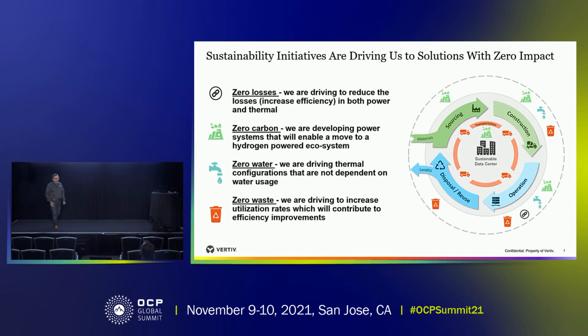One of the things we talk about a lot is UPS efficiency, or power system efficiency. You might see numbers quoted at 96% or 97%. For us, we're really focused on reducing those losses. You can have a 1% increase in efficiency, but that could mean a 30% improvement in your losses. The other thing is zero carbon, right? We're always trying to get to zero carbon, and we're developing solutions in that area, both in cooling and thermal, that can help you achieve those goals.